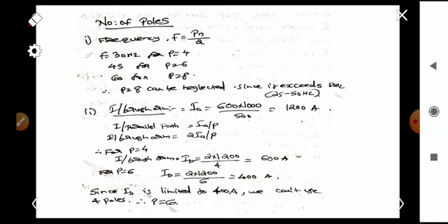we are going to find the current per brush arm. So here, current per brush arm, the equation is 2IA by P. If you select the number of poles equal to 4, we will get IB as 2 into 1200 by 4, so it is 600 ampere.